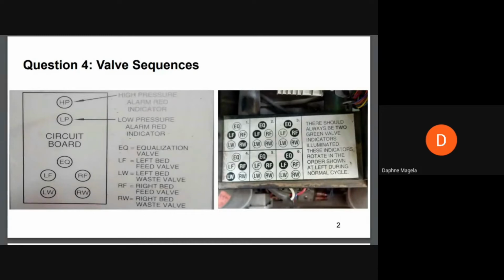Instead, they have an orifice, which is a small opening that restricts the flow of air. There is no equalization in the DeVilbiss. Instead, the orifice is used for purging. And purging is the process of using oxygen-enriched air from sieve bed A to flush out residual nitrogen from sieve bed B after wasting. Thanks, Maui.